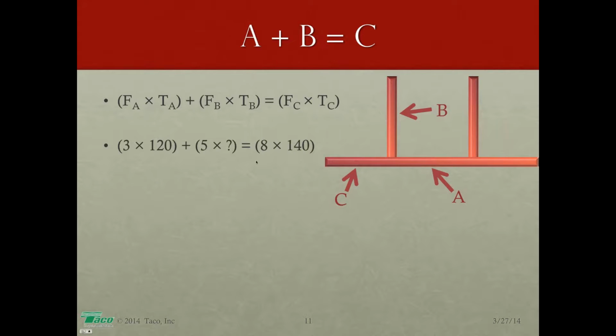The flow through A, as we recall from our last picture, was 3 gallons per minute, and the temperature was 120 degrees. The flow through B, which is coming out of the boiler, mixing in with that 120 degree water, is 5 gallons per minute, but we don't know the temperature. That's what we have to solve for. And then the flow and temperature in C, which is being distributed out to the heating system, is 8 gallons a minute, 140 degree water.